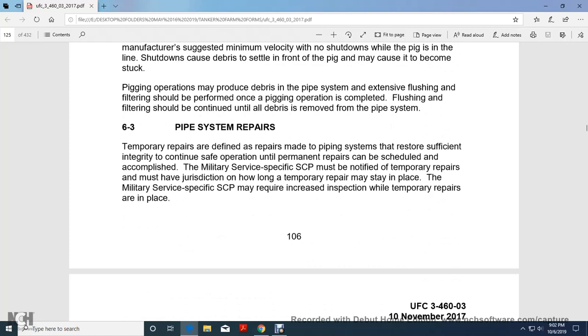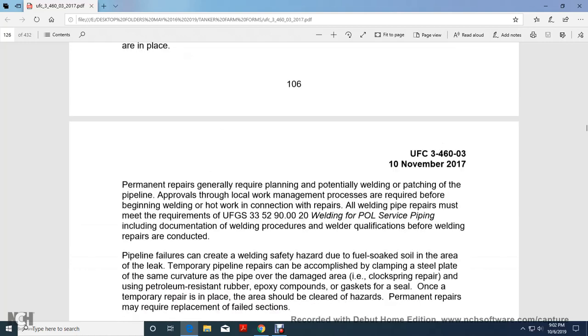6-3, pipe system repairs. Temporary repairs are defined as repairs made to the piping system to restore sufficient integrity for continuing safe operation until permanent repairs can be scheduled and accomplished. Certain control points must be notified, and the authority having jurisdiction determines how long the temporary repairs may stay in place. The control point may require inspection where the temporary repairs are in place.